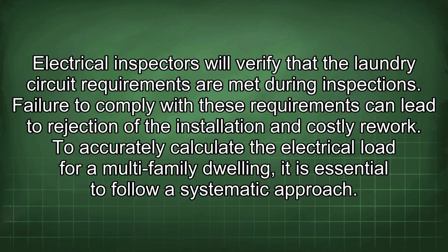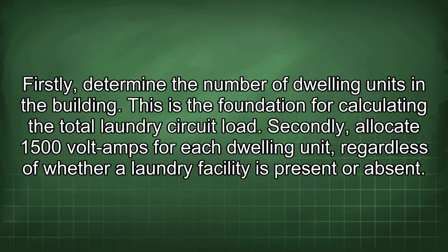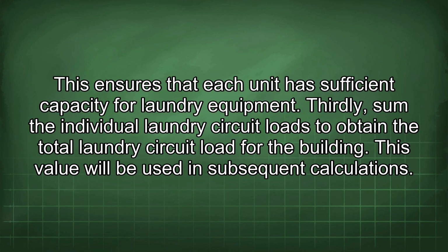To accurately calculate the electrical load for a multi-family dwelling, it is essential to follow a systematic approach. Firstly, determine the number of dwelling units in the building. This is the foundation for calculating the total laundry circuit load. Secondly, allocate 1500 volt amps for each dwelling unit, regardless of whether a laundry facility is present or absent. This ensures that each unit has sufficient capacity for laundry equipment. Thirdly, sum the individual laundry circuit loads to obtain the total laundry circuit load for the building. This value will be used in subsequent calculations.